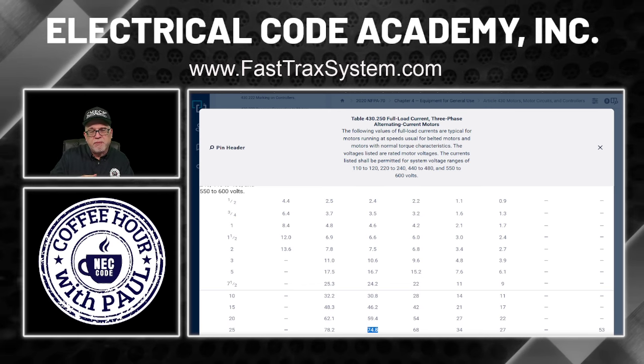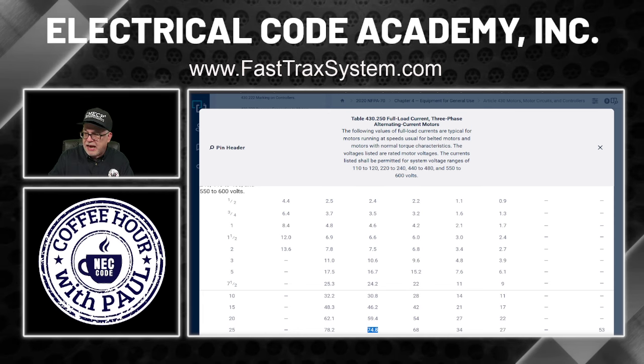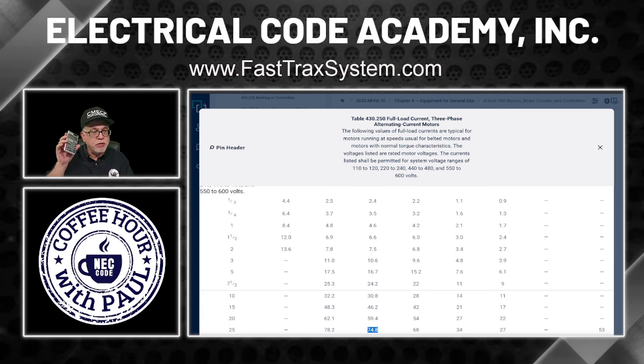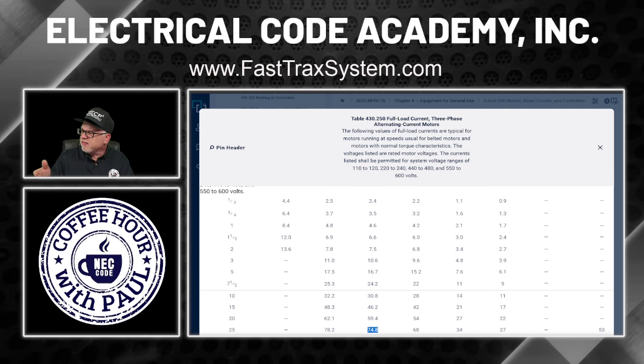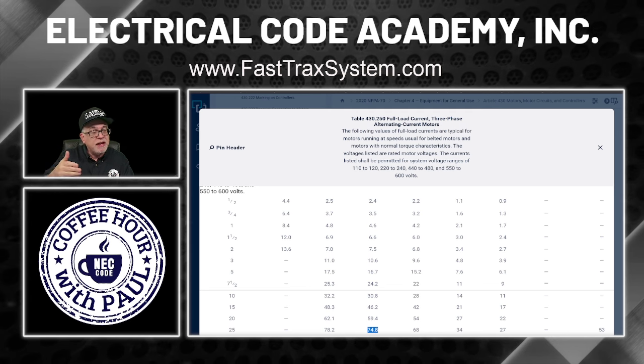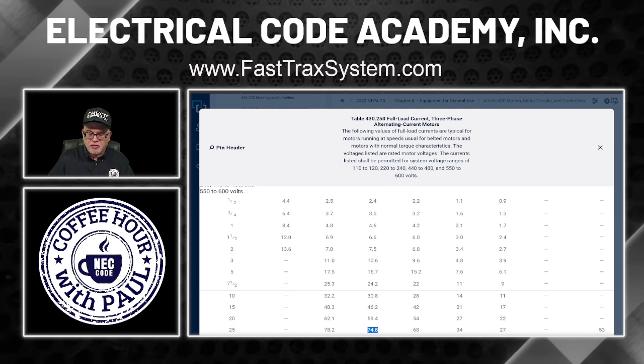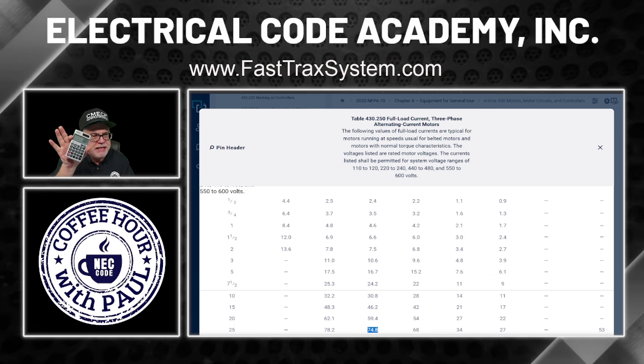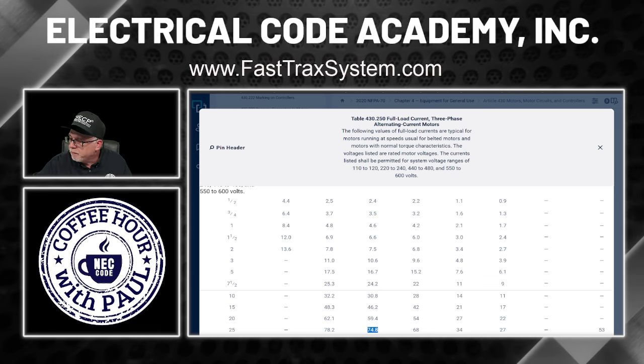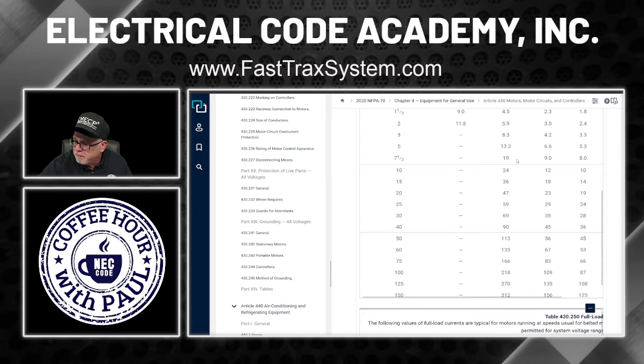Remember what it said back in 430.24? You basically take 74.8 times 1.25, that is 93.5, plus 100% of the FLC of the second motor, which is 74.8, and that is 168.3. Okay, well, we get to drop the 0.3, so we're going to come back to our course here. Get me back to the lesson.